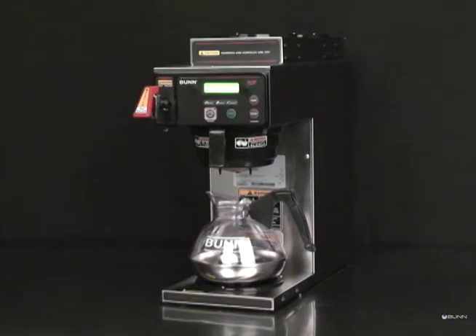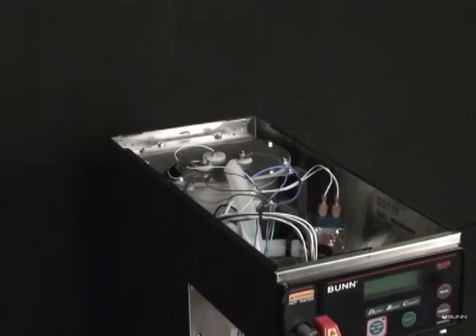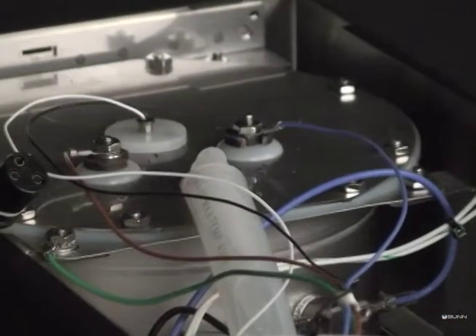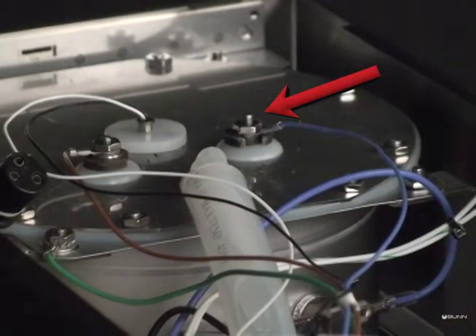This video will demonstrate how to adjust the refill threshold to variable water conditions and how to utilize the numbers for troubleshooting the refill circuit for an open or shorted circuit. Reverse osmosis filter systems and water in different geographical locations can have different conductivities. By adjusting the refill threshold menu according to water condition, the brewer refill circuit will be able to perform without error during normal operation of refilling the water tank.